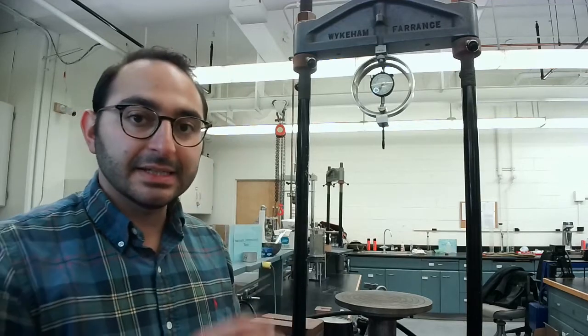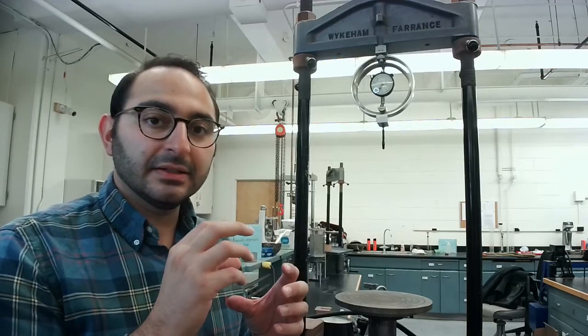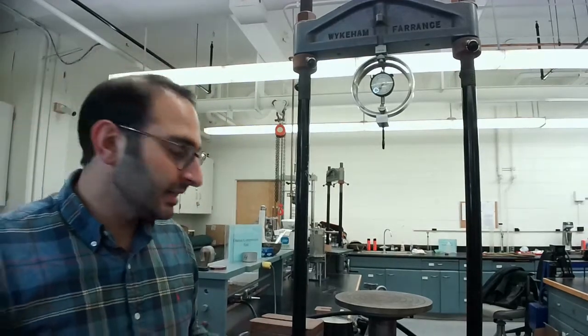The calibration factors we're trying to obtain today will be a constant having a particular unit. If you multiply it into displacements that you later record, it will eventually give you load in units of load. So what we want to get today is that constant coefficient that you'll multiply later on.